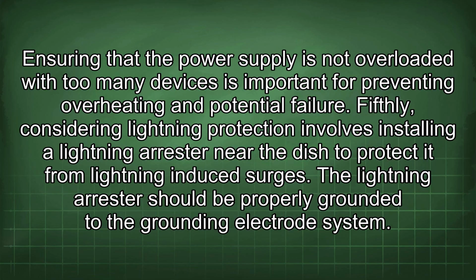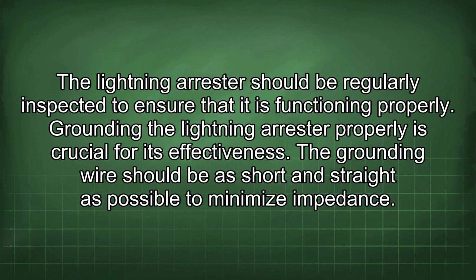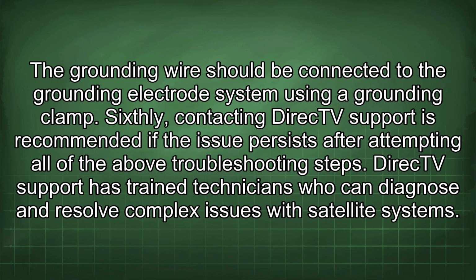Fifthly, considering lightning protection involves installing a lightning arrestor near the dish to protect it from lightning-induced surges. A lightning arrestor should be properly grounded to the grounding electrode system. A lightning arrestor should be regularly inspected to ensure that it is functioning properly. Grounding the lightning arrestor properly is crucial for its effectiveness. The grounding wire should be as short and straight as possible to minimize impedance. The grounding wire should be connected to the grounding electrode system using a grounding clamp.